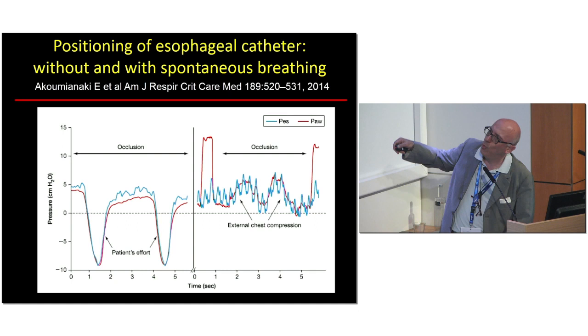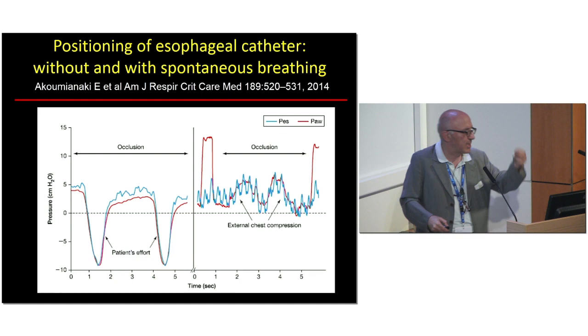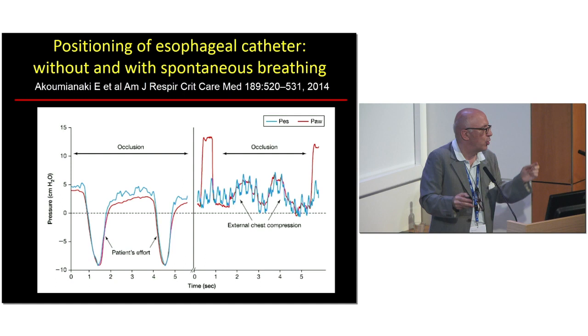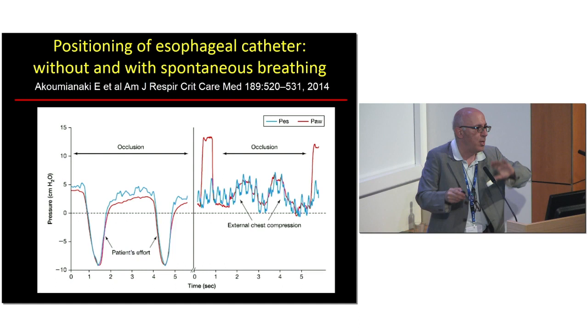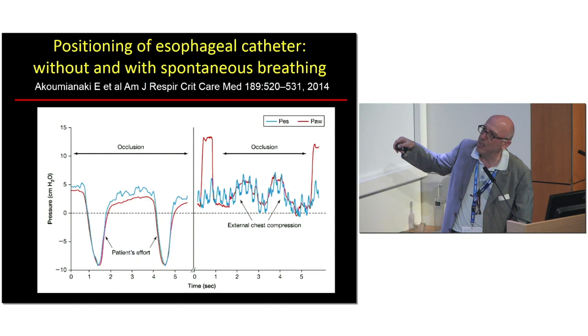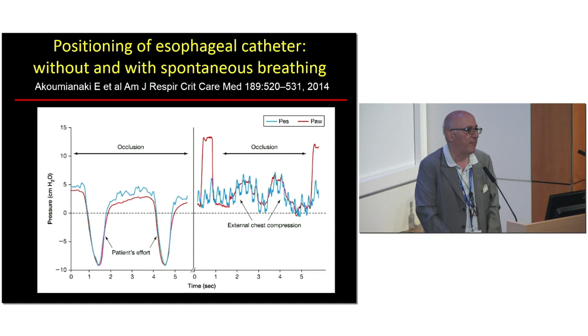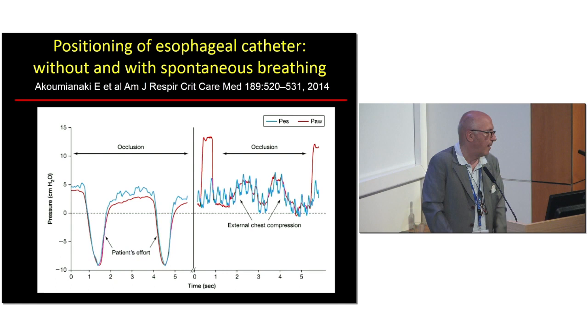This is the occlusion test, during which you occlude the airways. The patient is spontaneously breathing. In blue you have the esophageal pressure, in red is the airway pressure. If you assume the balloon is correctly positioned, at the occlusion you have no change in volume. That's correct, so the transpulmonary pressure should not change. Do you follow me? You are occluded, no change in volume, no change in transpulmonary pressure. So it means the swings in esophageal pressure should be exactly the same as the swings in the airway pressure, or at least within 10%.